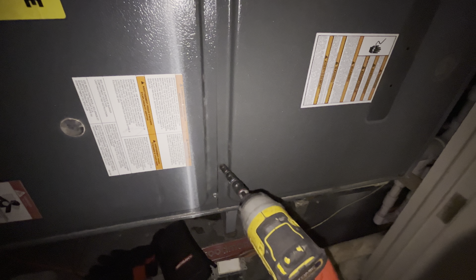So there is your flame rollout switch. And there's 2 of them in there. There's one in the bottom and one up top. This switch is a manual reset. So I'm gonna hit this one. First of all, I'm gonna turn this thing off. So flame rollout, that's 6 flashes. I'm gonna go ahead and see if it's this one that's tripped.